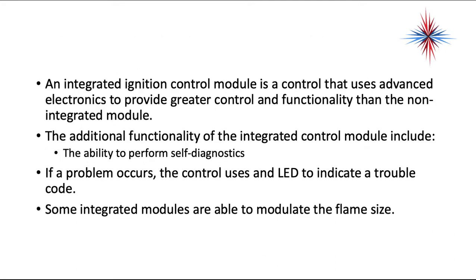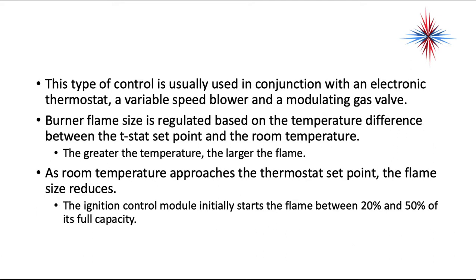An integrated ignition control module is a control that uses advanced electronics to provide greater control and functionality than the non-integrated module. This additional functionality includes the ability to perform self-diagnostics. If a problem occurs, the control flashes an LED to indicate a trouble code. Some integrated modules are even able to modulate the flame size. This type of control is usually used in conjunction with electronic thermostats, a variable speed blower, and a modulating gas valve. Burner flame size is regulated based on the temperature difference between the thermostat's set point and the room temperature.